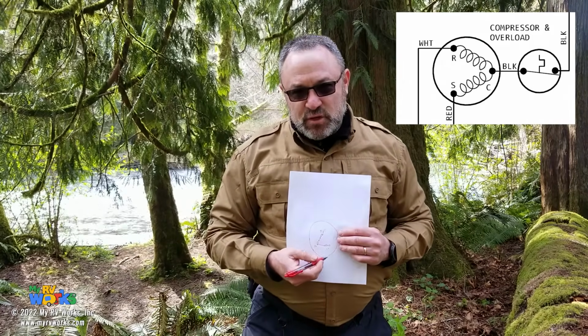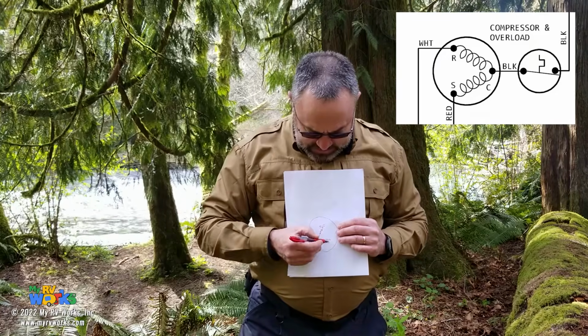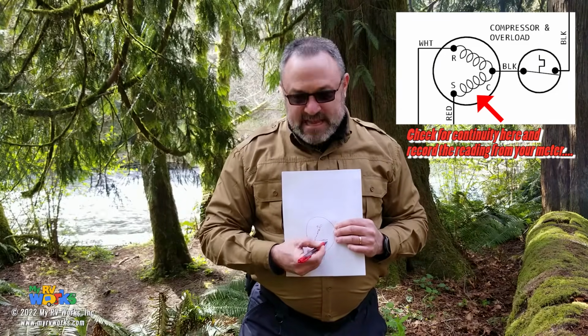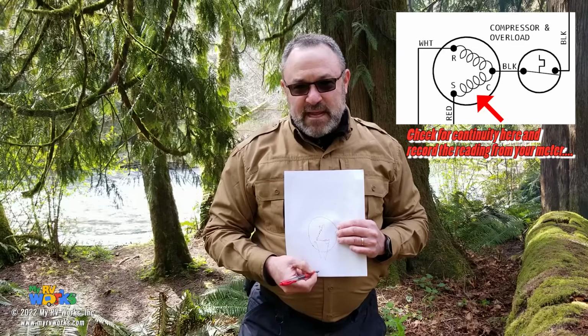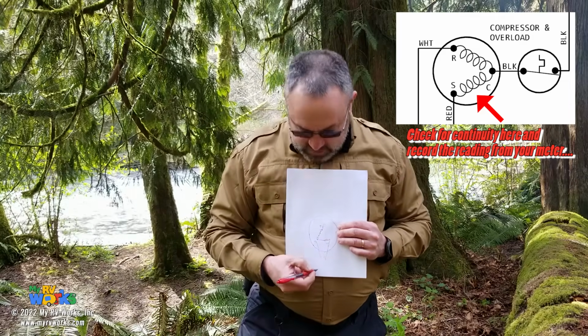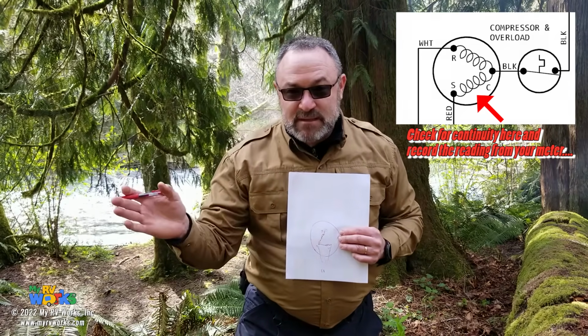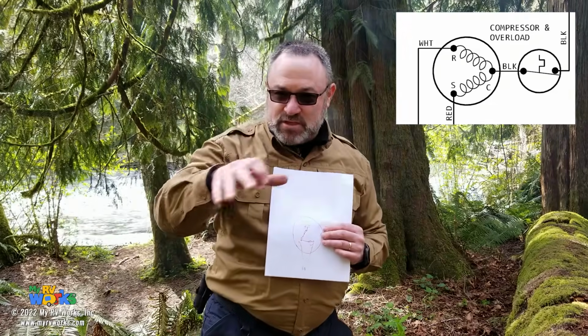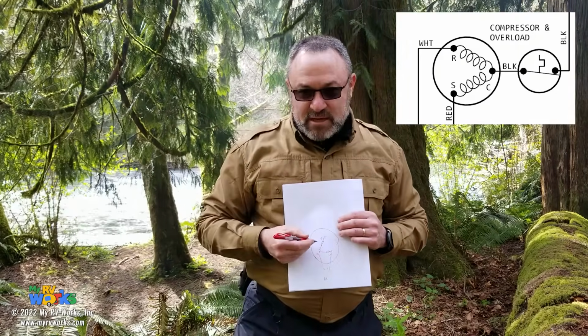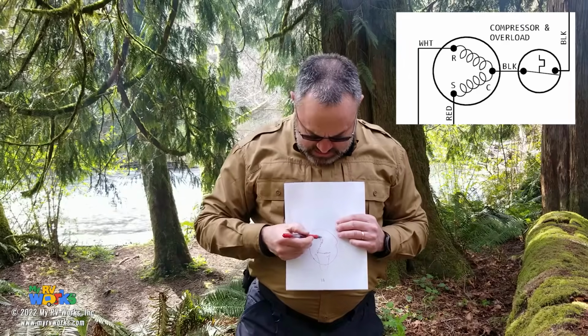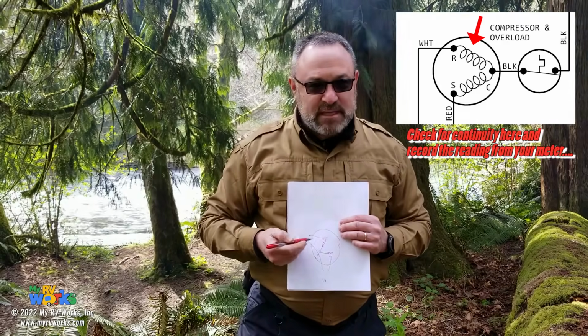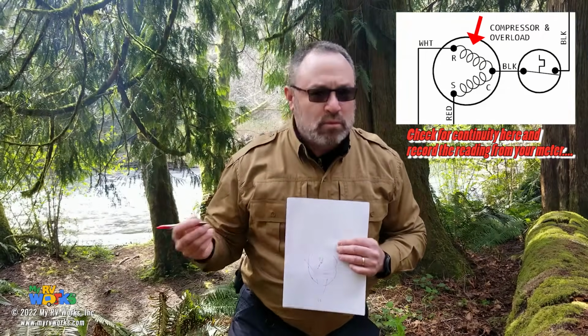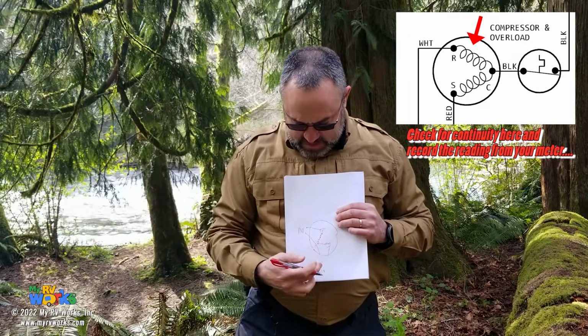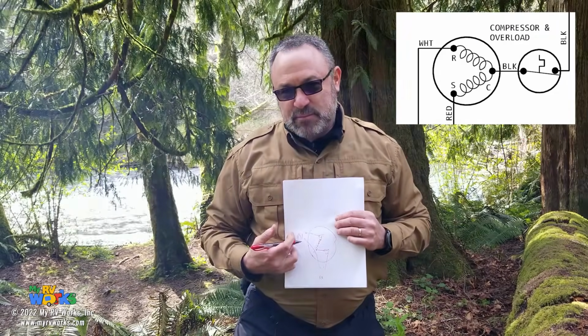So what I need you to do with your meter is check the continuity between the S and the C and write that down. I'm going to come up with a number 5, okay? I don't even know if that's even close to the number, but for mathematical purposes, go with me on this. Then take your meter, this is on top of your compressor, and check it from the run and the common, and let's say you get 2. So in this one you got a 5, this one you got a 2.